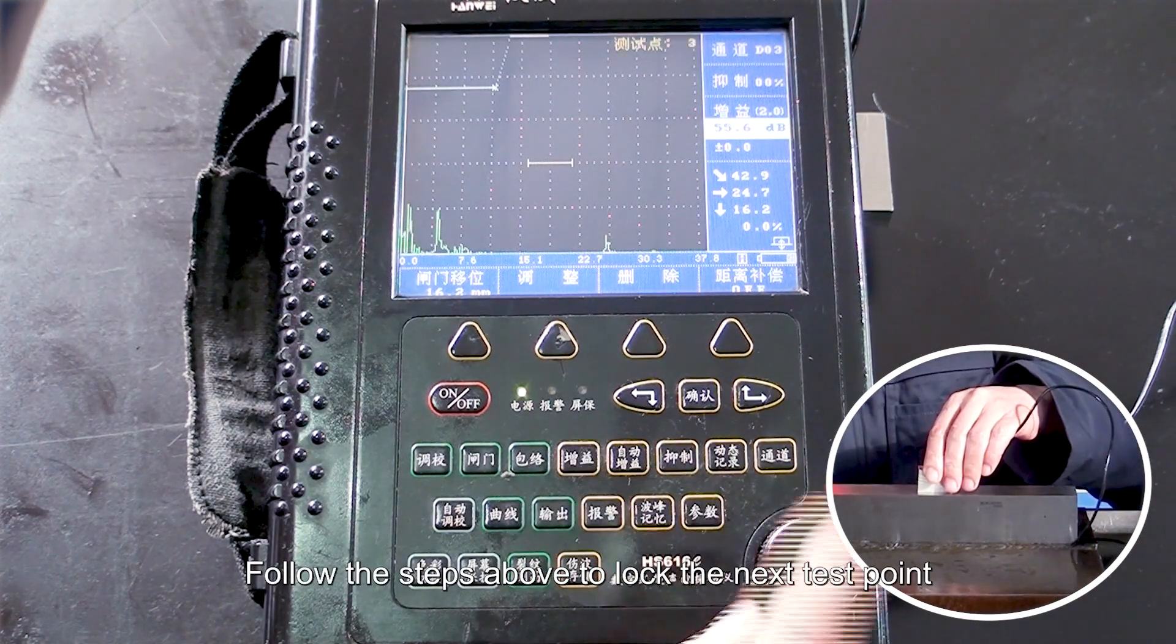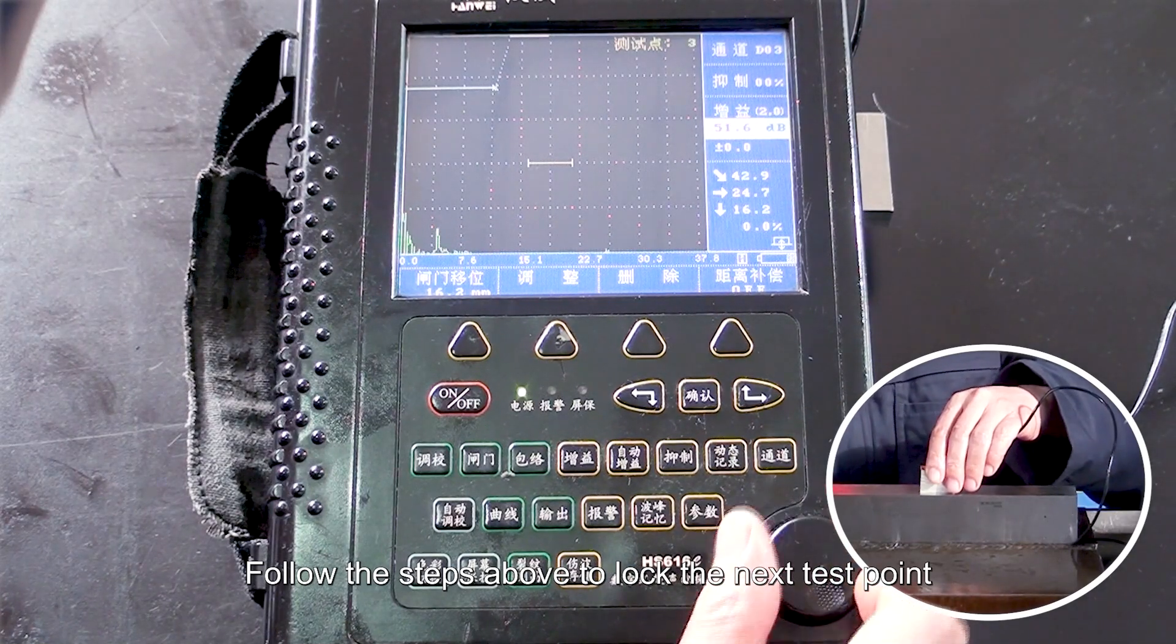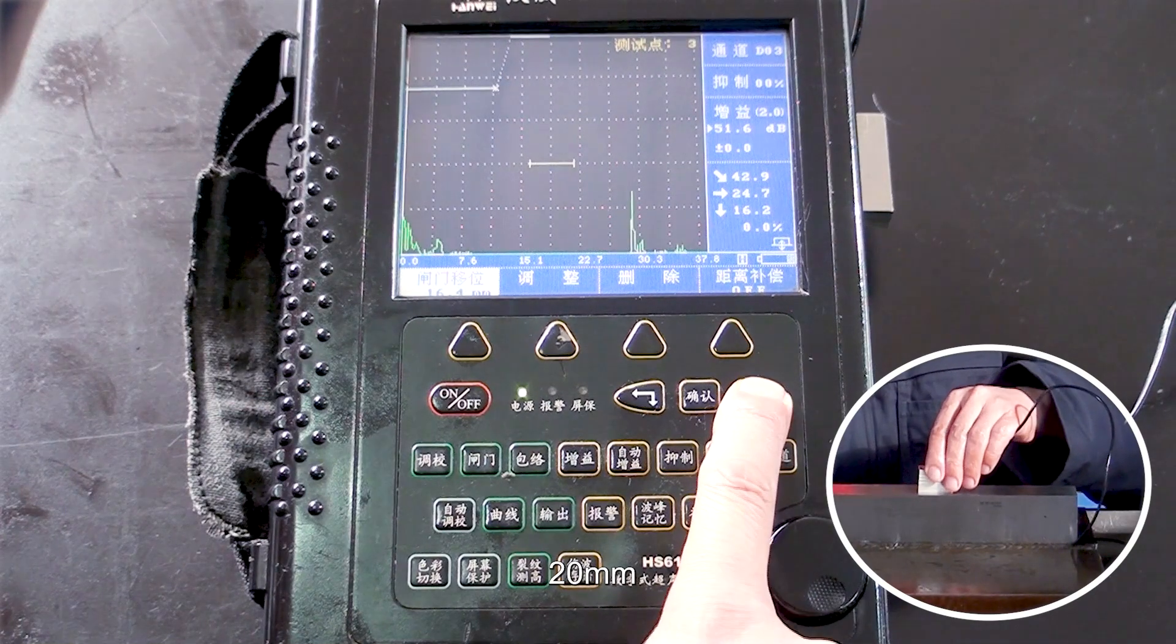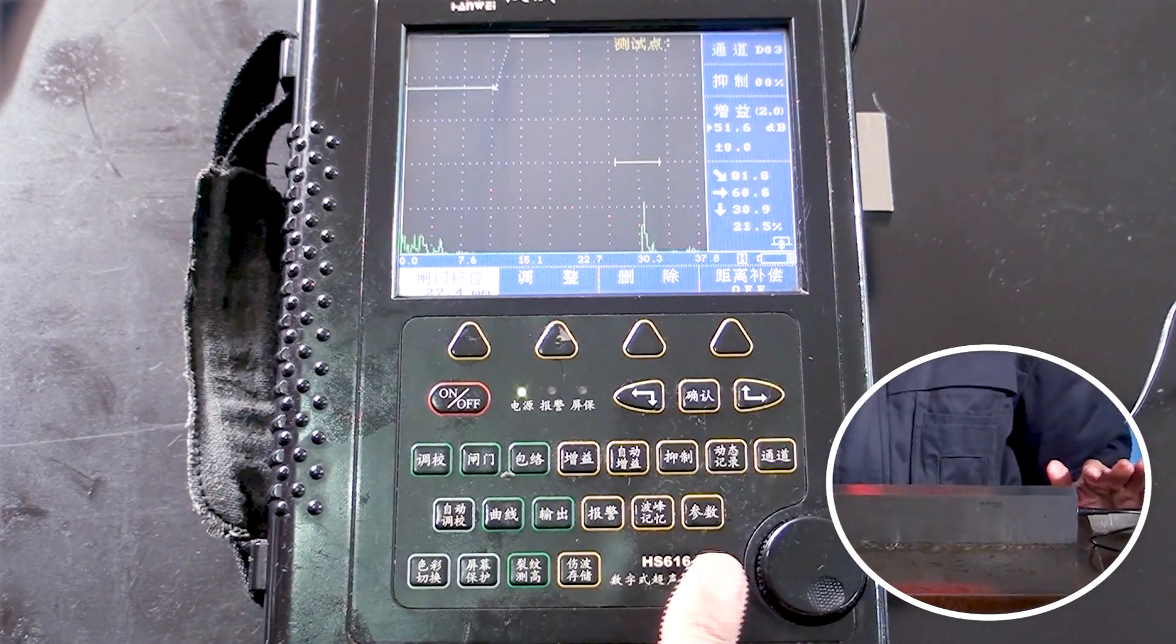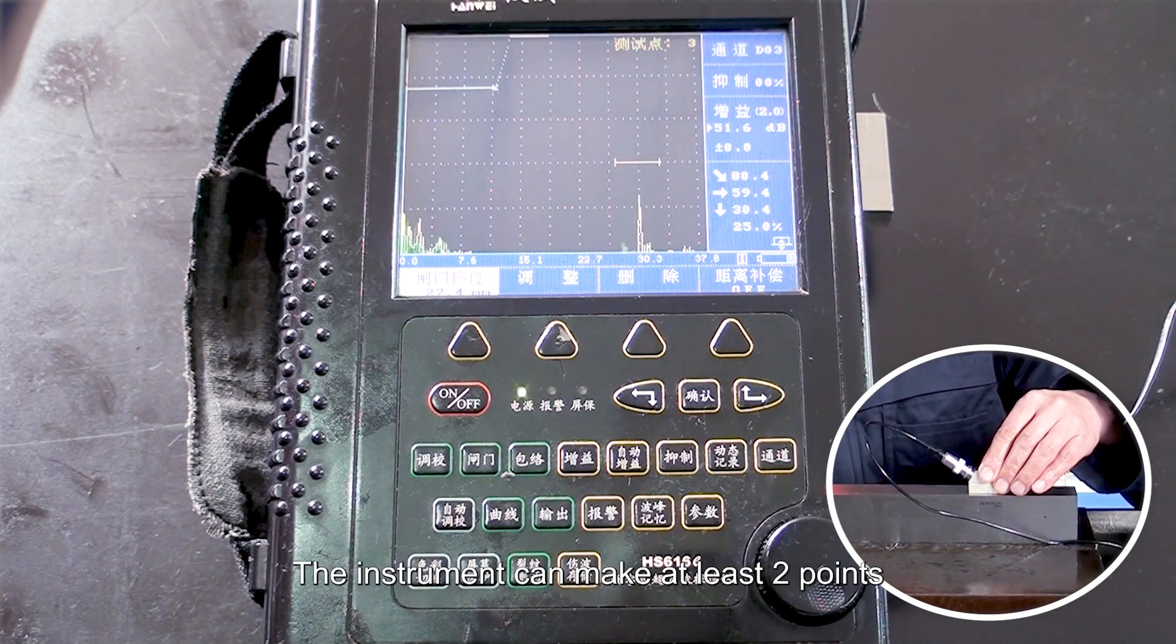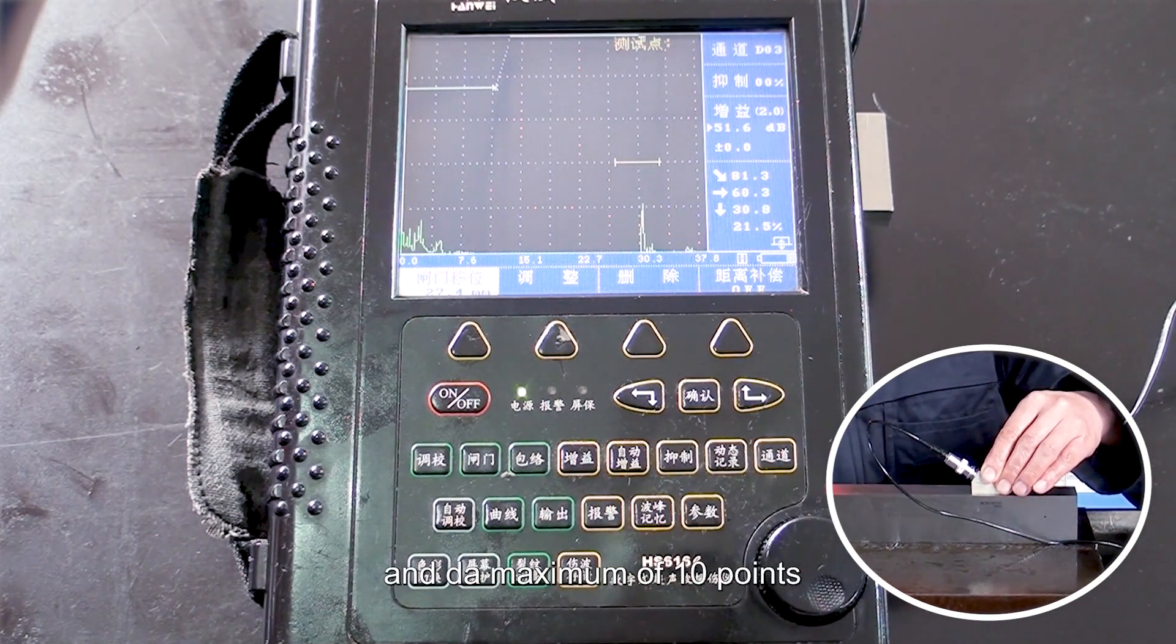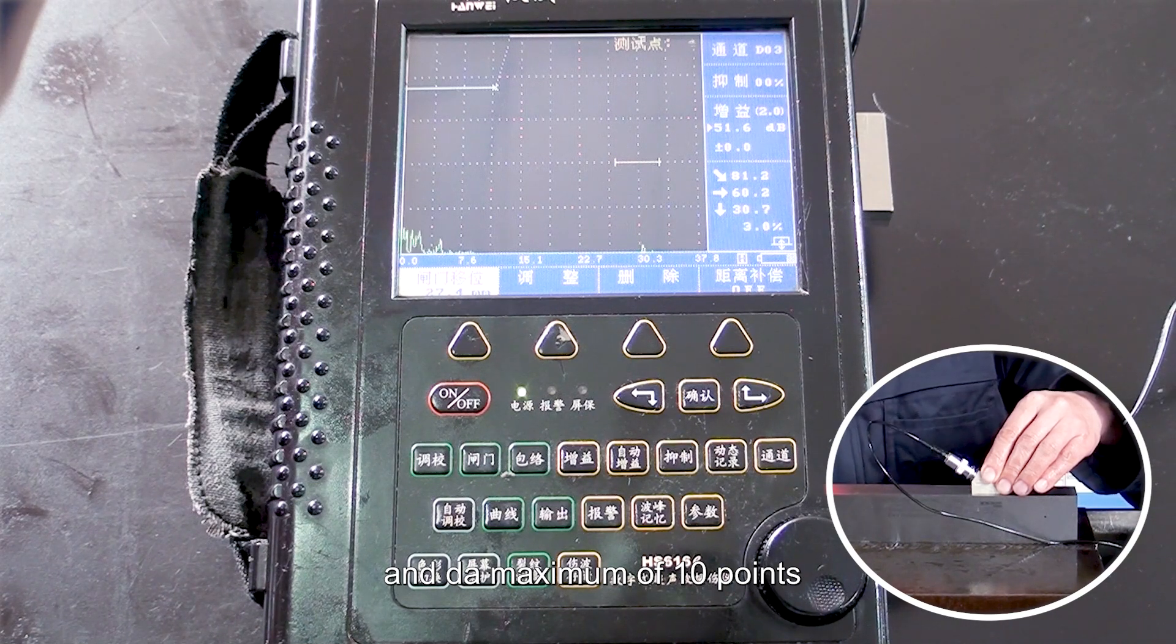Follow the steps above to lock the next test point, 20 mm, 30 mm, 40 mm. The instrument can make at least 2 points and a maximum of 10 points.